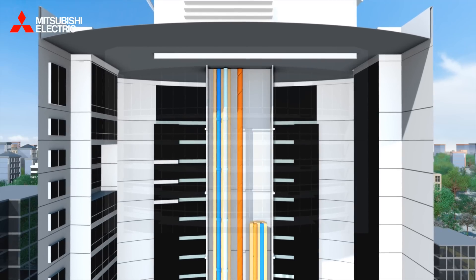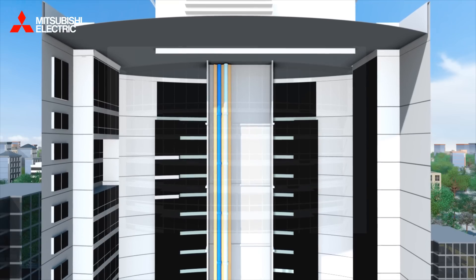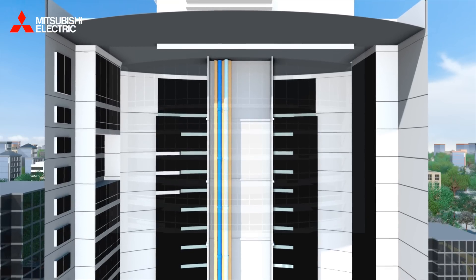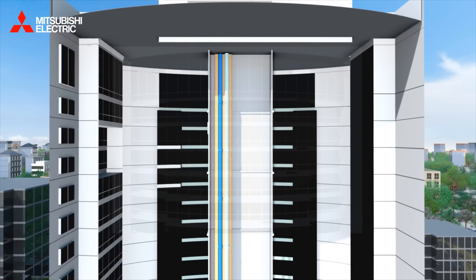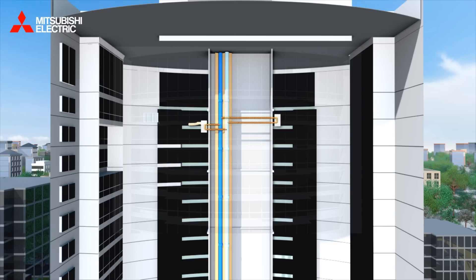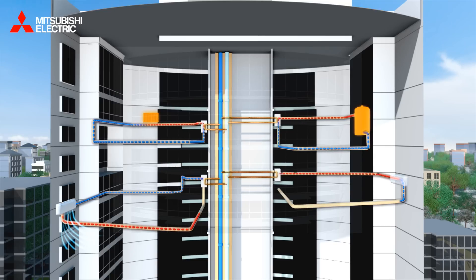With a single energy loop, we can remove the need for a high temperature riser, remove the need for a boiler flue, and use a re-engineered chilled water riser to meet all of the heating, cooling and hot water requirements using heat pump technology. Individual circuits can join to this energy loop to add or extract heat from it, giving us a more balanced use of technology throughout the building.